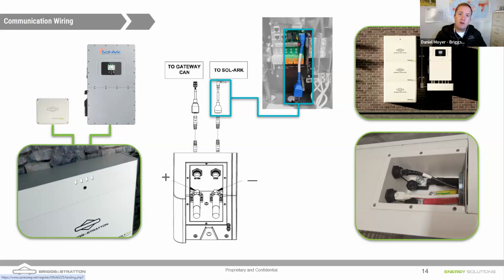Nathan, what's another option besides a microinverter or an optimizer that will still allow us to meet the rapid shutdown code? Yeah, so we can get just specific rapid shutdown devices. Tigo is a very common one that is used. AP Smart rapid shutdowns can be used. And in fact, you can actually power the AP Smart transmitter, one transmitter, off of the Sol-Ark. I believe it's pins 17 and 18 or 15 and 16. I think you can power your AP Smart transmitter off of them.